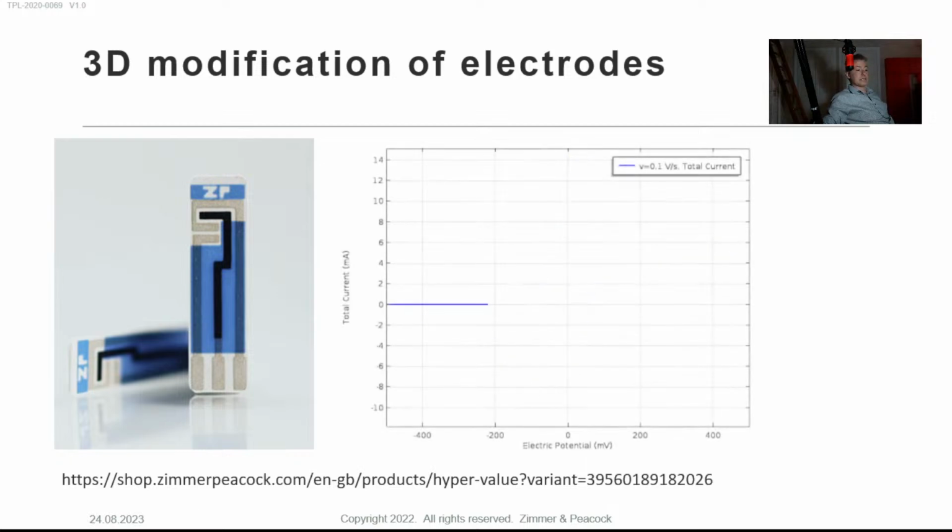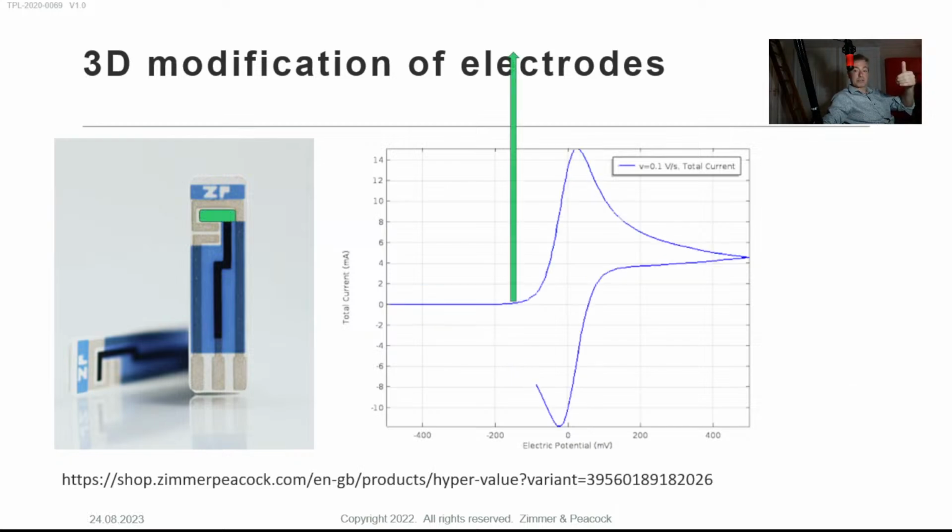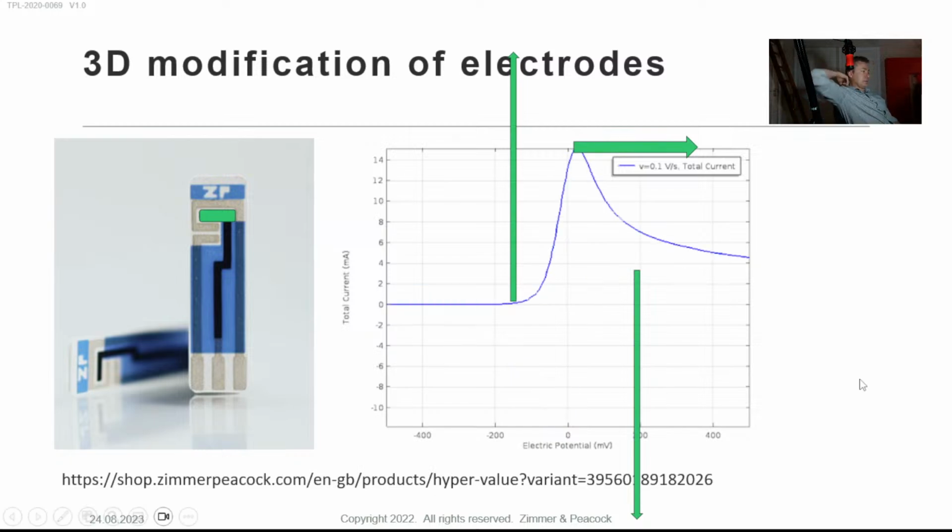And you can get a signal using ferrocyanide. I do have a link to that solution below, but this is a fairly standard electrochemical procedure. So you baseline yourself using standard chemicals, then you modify it, and when you've modified it, I suspect that the peak height will go up, and I suspect that the peaks will shift. The reason they'll shift is because you're pushing more and more current through the circuit, and you'll suffer from something called IR drop. You can then instigate IR compensation.